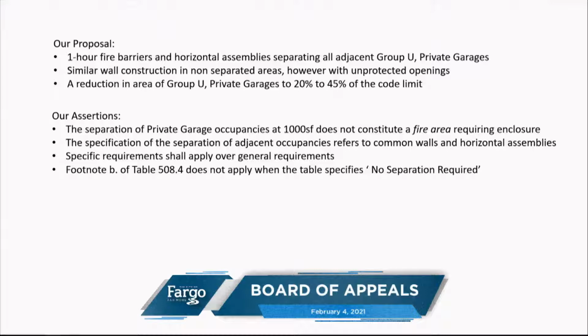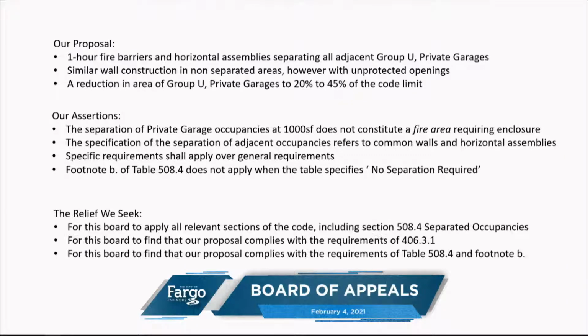Specific requirements shall apply over general requirements as stated in Chapter 1, and footnote B of Table 508.4 does not apply when the table specifies no separation requirements. So the relief that we seek today is for this board to apply all relevant sections of the code, including Section 508.4, separated occupancies. For this board to find that our proposal complies with the requirements of 406.3.1, and for this board to find that our proposal complies with the requirements of 508.4 and footnote B. Thank you for your consideration.